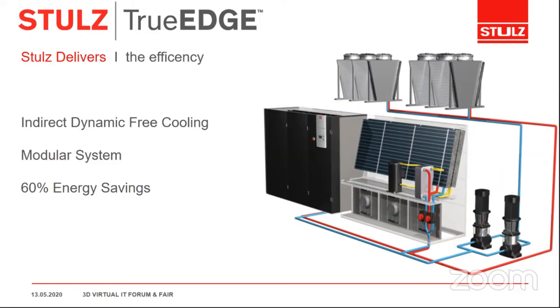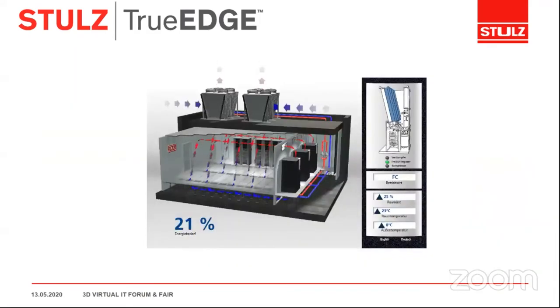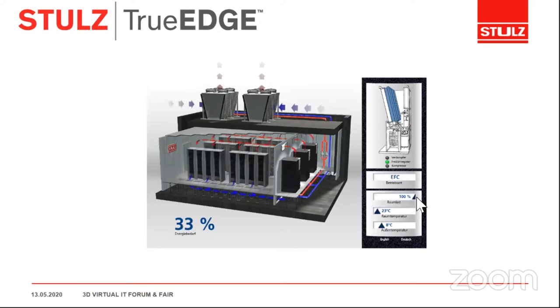And how does it work? I will show you on this slide. For example, we've got the room with a heat load of 100%. Let me adjust the room air temperature. I also recommend setting the room temperature as best as possible, not as low as possible. I will put it to 25, and I will set the outside temperature high, for example in summer.